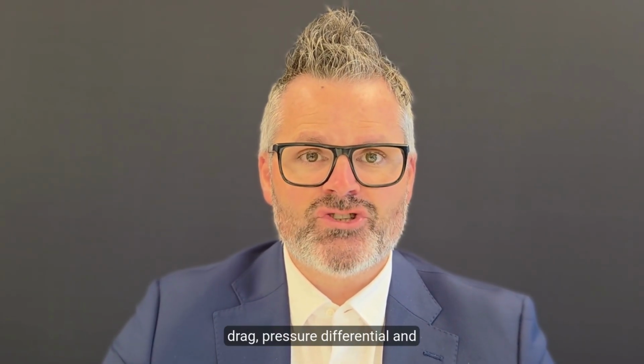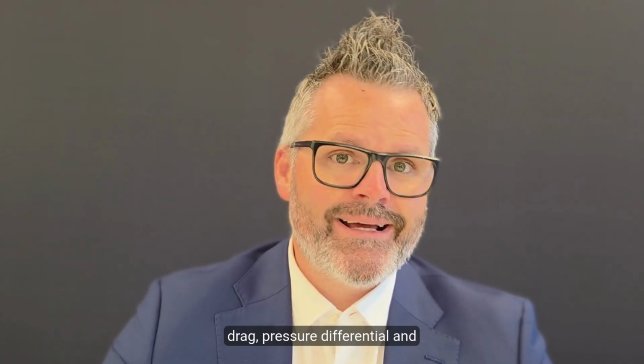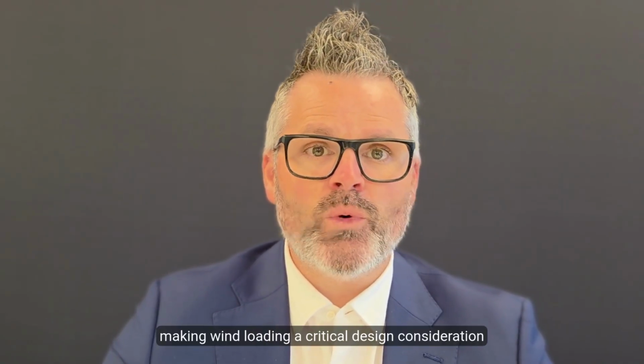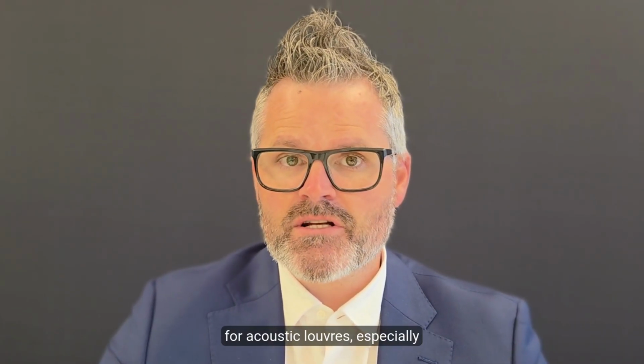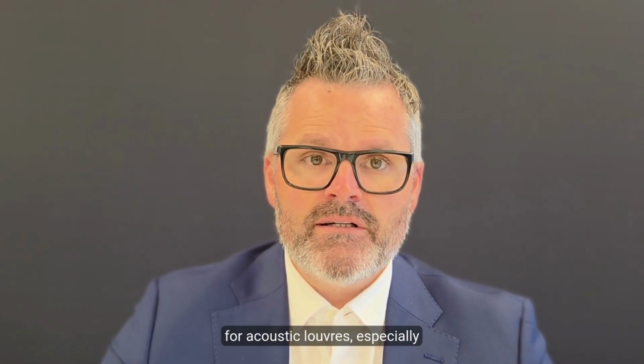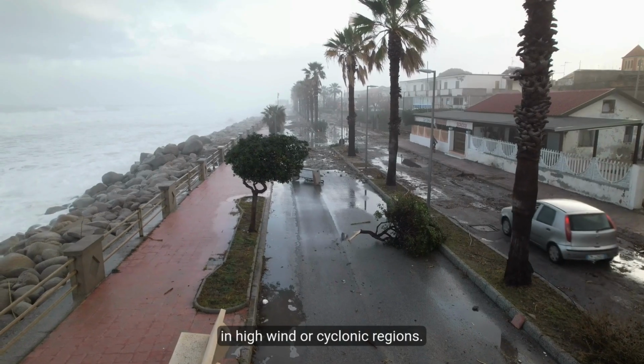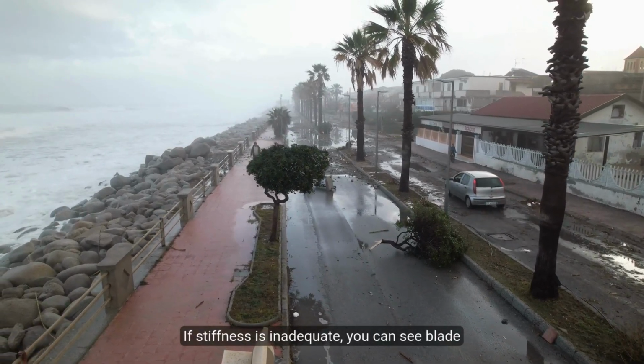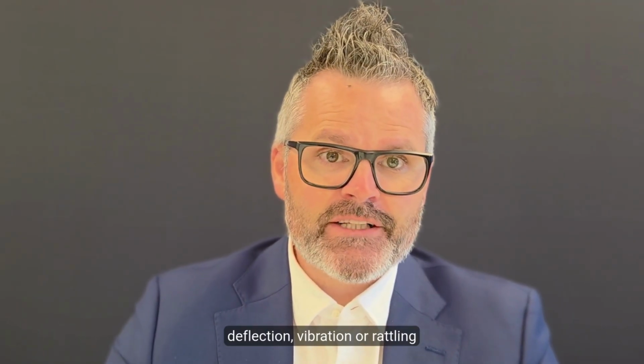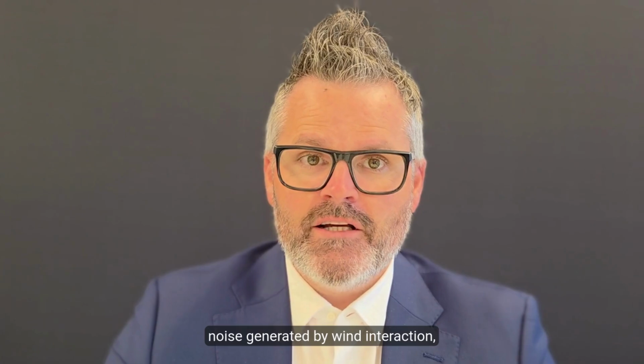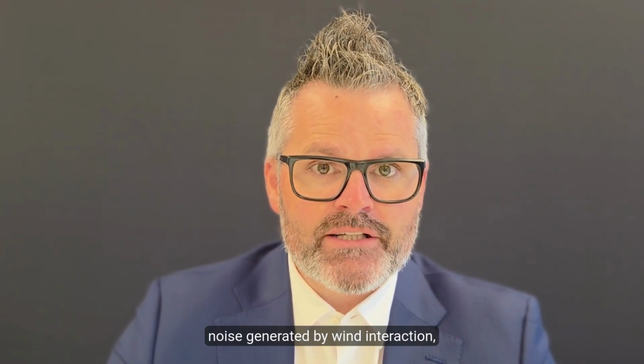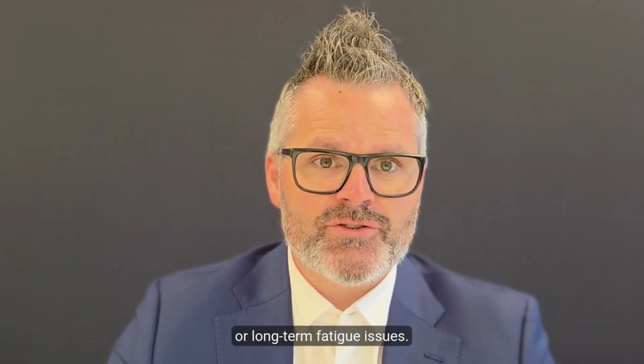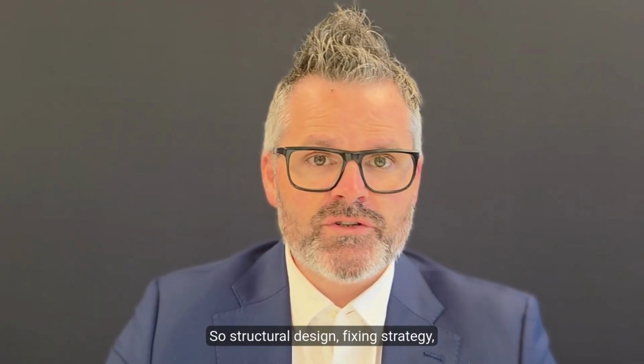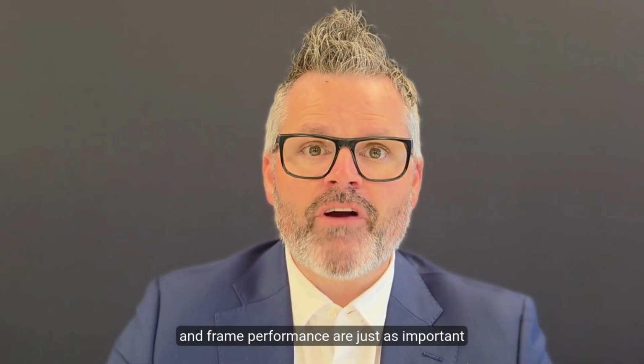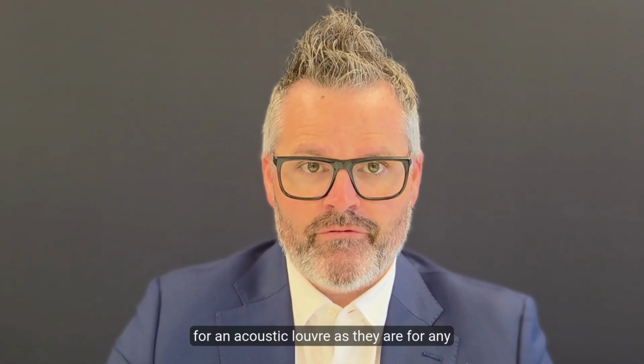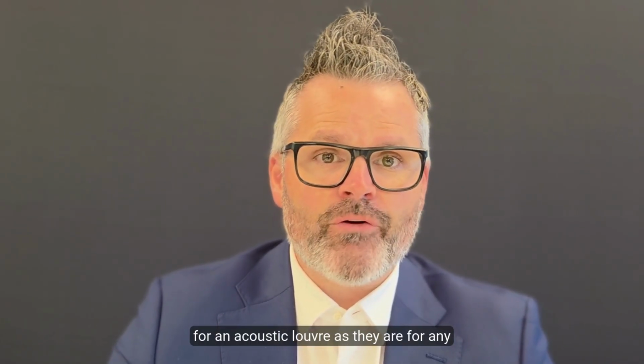These factors increase drag, pressure differential, and bending moments, making wind loading a critical design consideration for acoustic louvres, especially in high wind or cyclonic regions. If stiffness is inadequate, you can see blade deflection, vibration or rattling, noise generated by wind interaction, or long-term fatigue issues. So structural design, fixing strategy, and frame performance are just as important for an acoustic louver as they are for any other facade element.